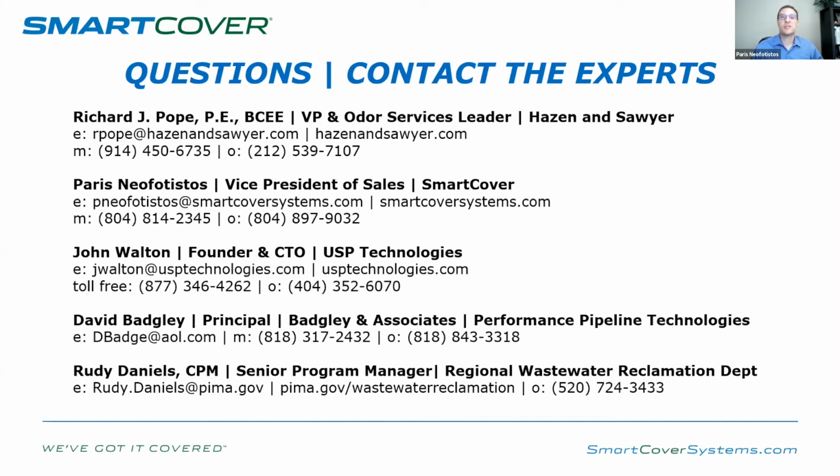Yeah, good question. So some of it is just related to making sure that the sensor is placed in a location where it's typically not going to be submerged by the wastewater. The usual guidance is to put it 6 to 8 feet above the liquid level if possible, where it's not going to be submerged under normal operating conditions. You also want to look for locations where you have known H2S odor complaints or releases. Those are obvious locations to choose.